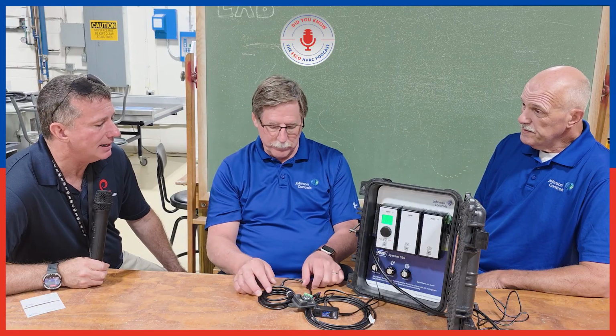When you're talking about refrigerant leaks, you want something that's not only reliable but extremely fast. I've seen a lot of our refrigerant, even our portable refrigerant leak detection devices, go into this technology. It's really smart when we think about it. Many of our previous sensors had heated components, whether they reached a high temperature threshold or not. As we start looking at sensors detecting potentially mildly flammable gases, using a technology that's low temperature as well as lower current just makes for a smarter decision going forward, I think, personally.